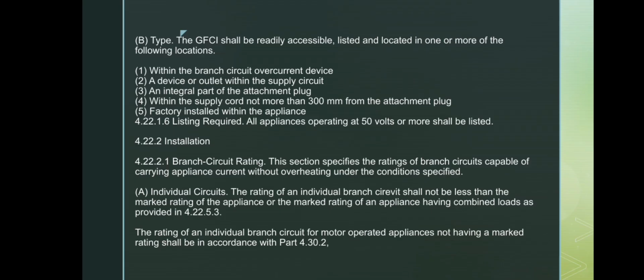Next, the GFCI must be easy to access, properly listed, and installed in any of these allowed locations: inside a branch circuit overcurrent device, in a device or outlet on the supply circuit, built into the attachment plug, within the supply cord not more than 300 mm from the plug, or factory installed inside the appliance. All appliances operating at 50 volts or more must be listed.